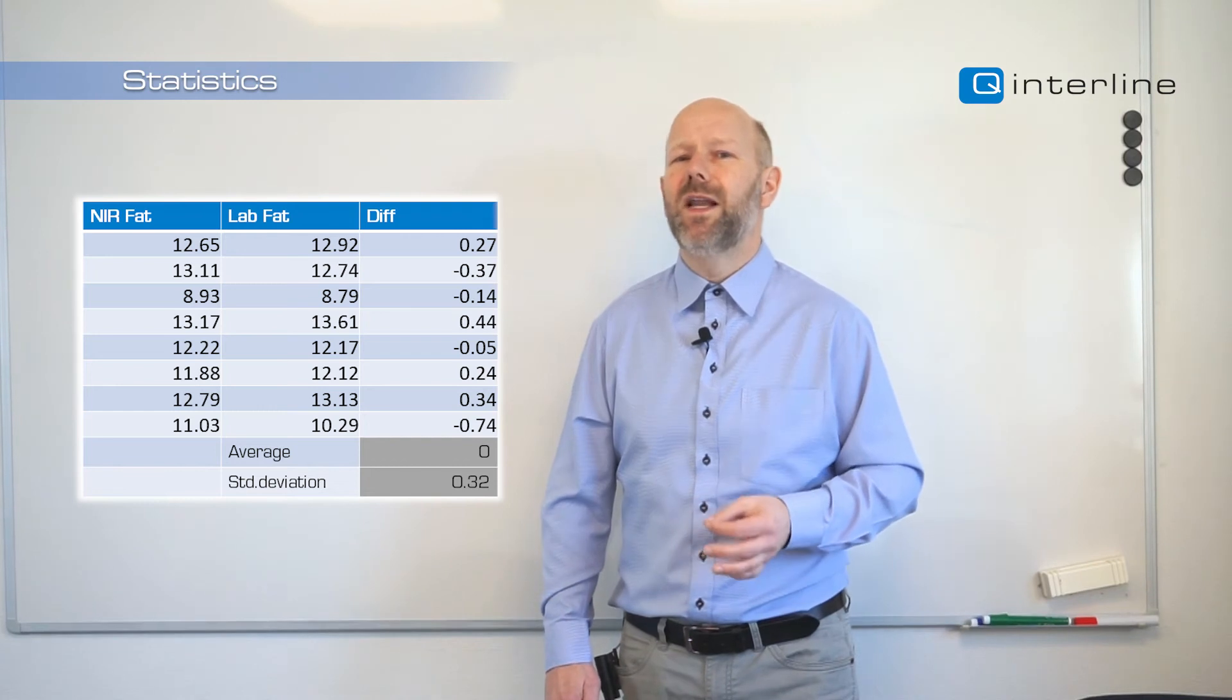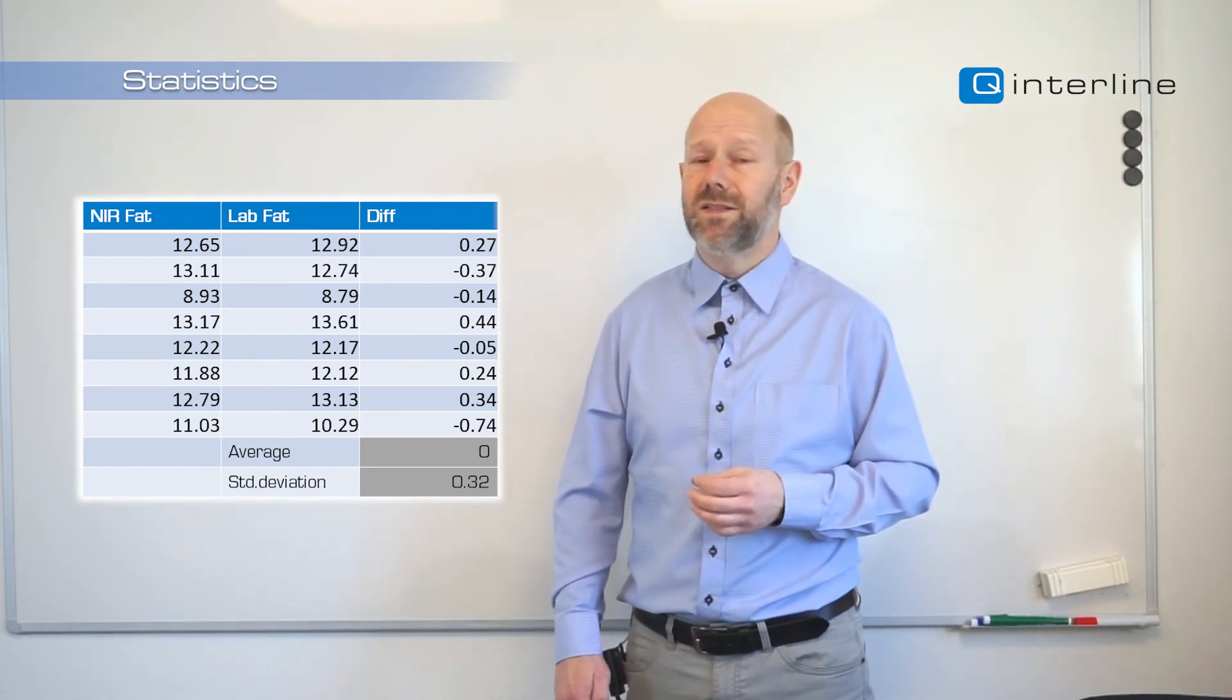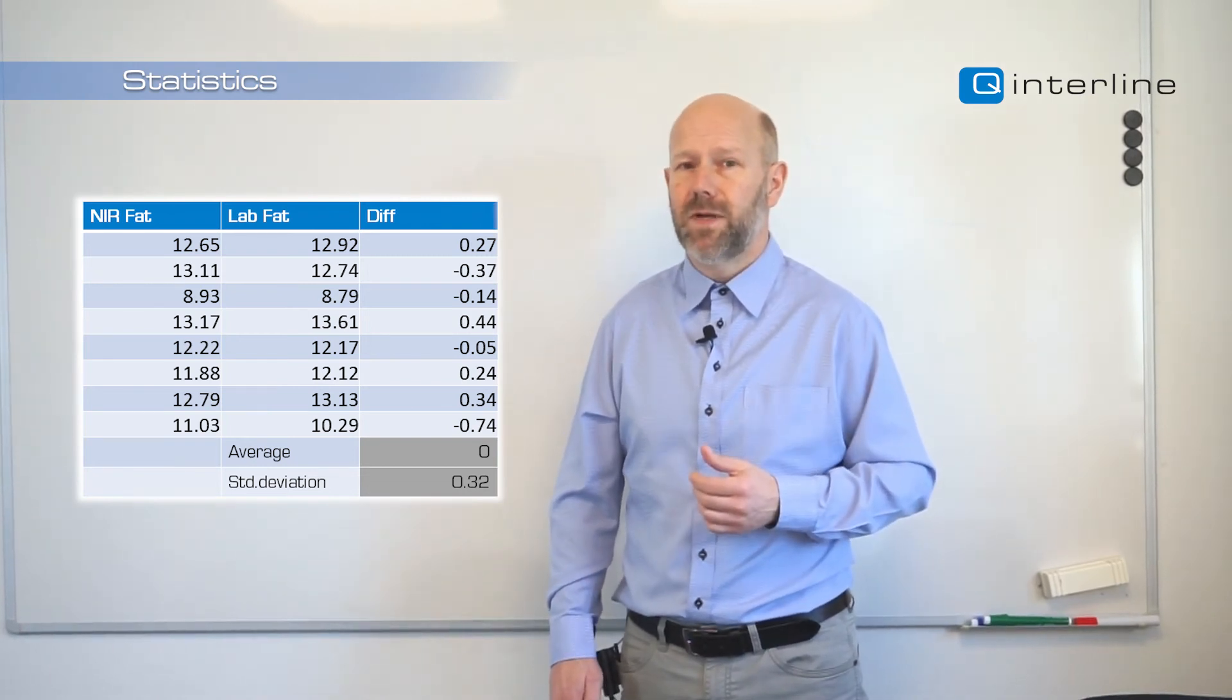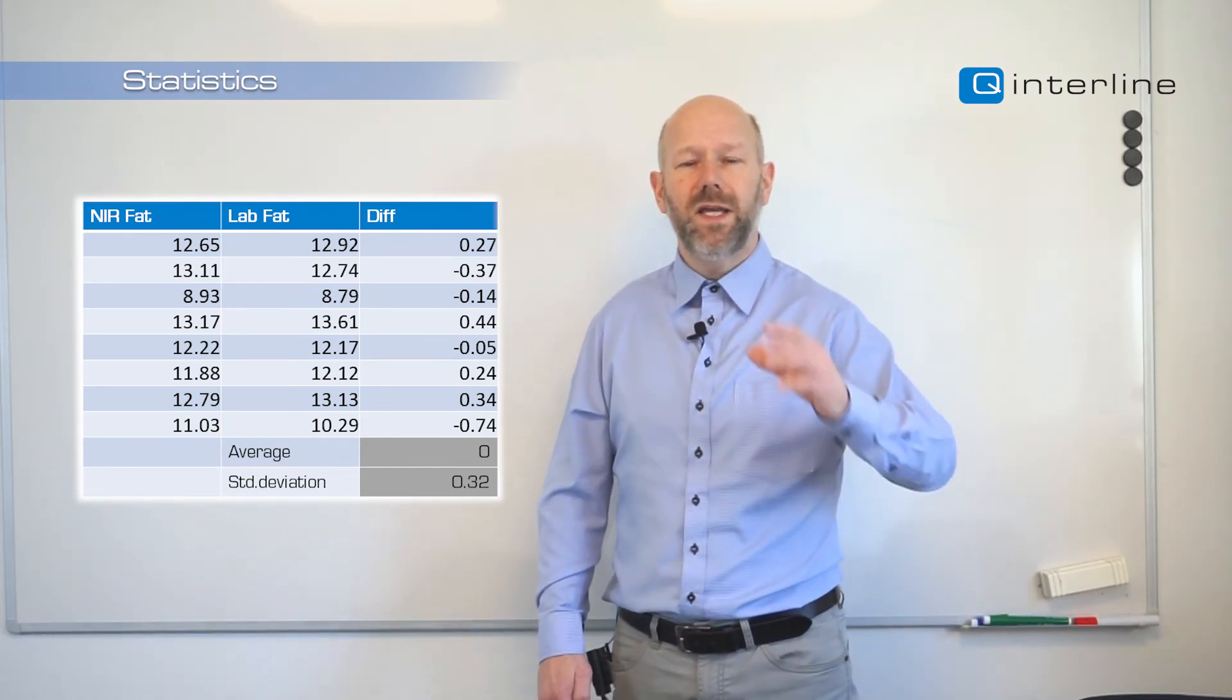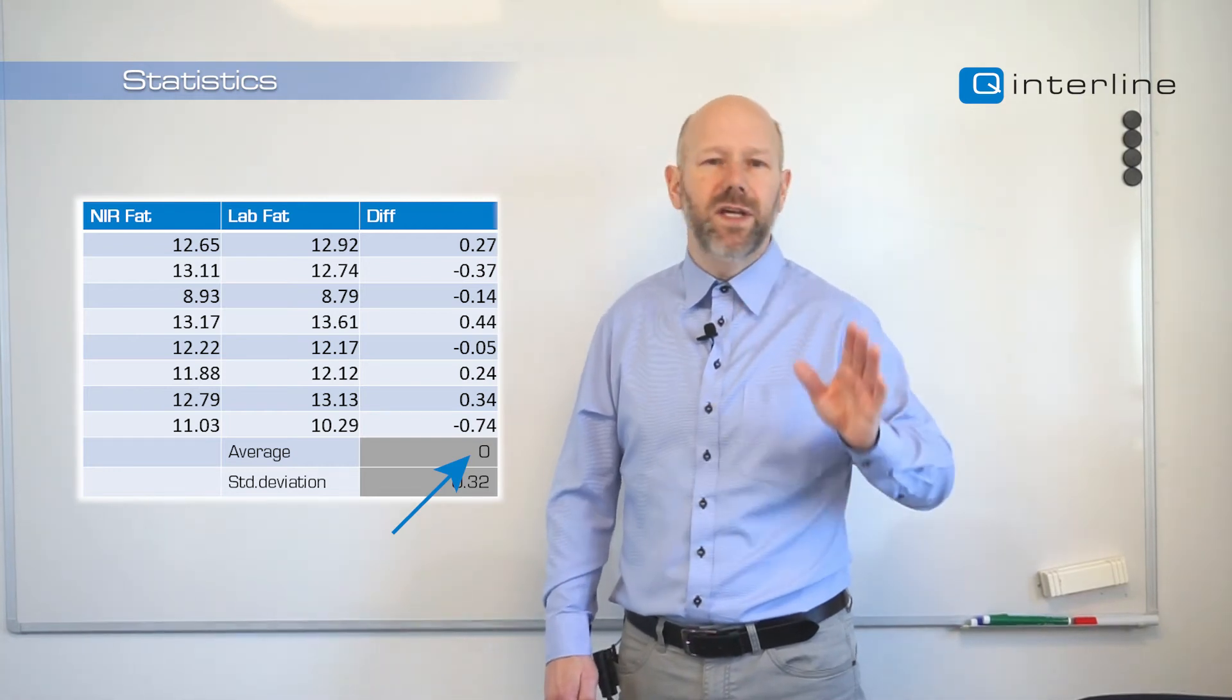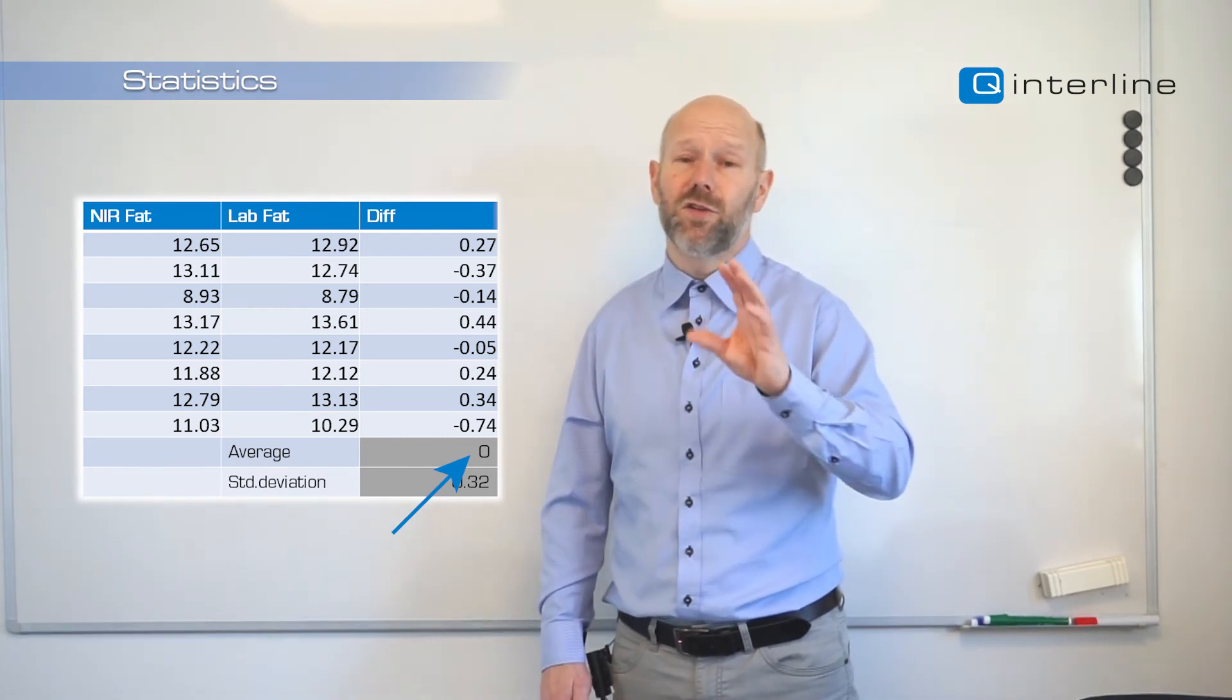We can see when we validate that the NIR gave certain fat numbers, the lab gave other fat numbers, and we see that they are not identical. Some of the differences are very small, some of them are higher. But that's statistics. We can observe with Excel or other means, we can calculate the average error. In this case, it's zero. It's of course constructed. We'll never hit zero in real life, especially if the data set is as small as this one. Be careful with false biases on small data sets.